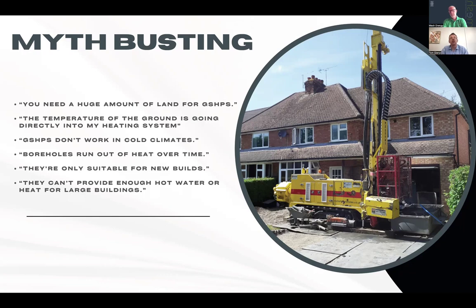In a traditional house, you are extracting heat in autumn, winter and then spring. But the system really slows down in the summer, and you're only still extracting some heat, mainly to generate hot water. So the extraction rate drops. That's when the borehole field has time to recharge and bring the energy, or the temperature, back to the area.